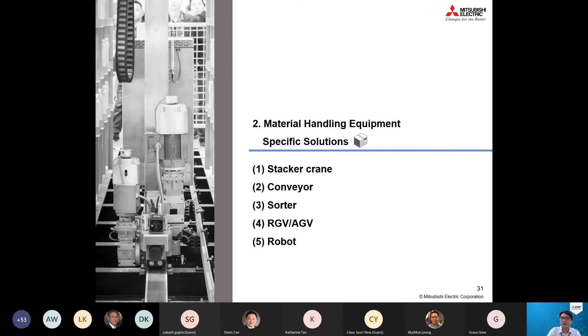Our solution here is using our inverter for stacker crane, the FR-A800-AWH model. This helps provide solutions through vibration control, position calibration functions that are much faster, and more stable loading and unloading operations. It also reduces development costs by using parameters built into the inverter, and uses the safety functions of the cranes to avoid problems.